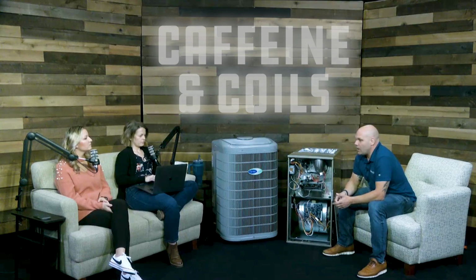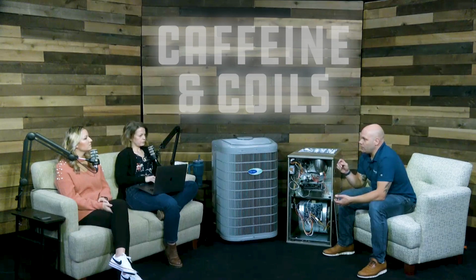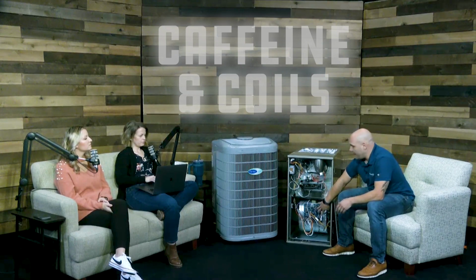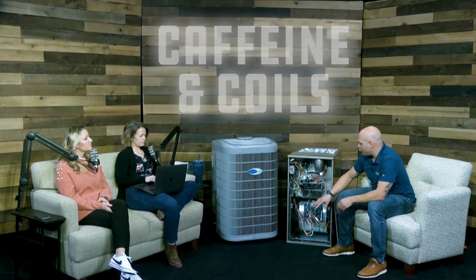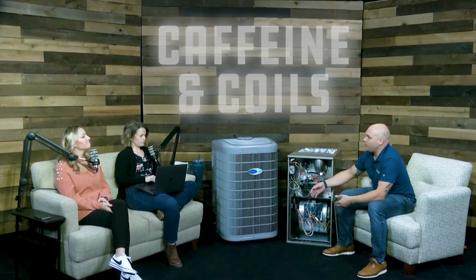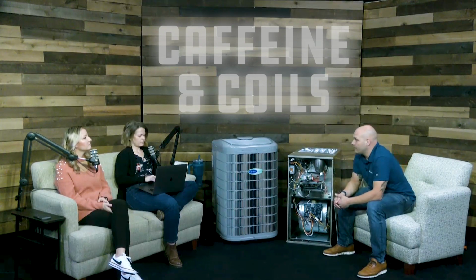We do offer training classes here at Mingledorff's to go over that particular setup. But make sure you have the Carrier service tool on your phone, and there is a new circuit board tab on it. Because these boards come blank, they don't know what model number or serial you're adding them to, so you have to program the board prior to putting it in. You would do that with the power off.